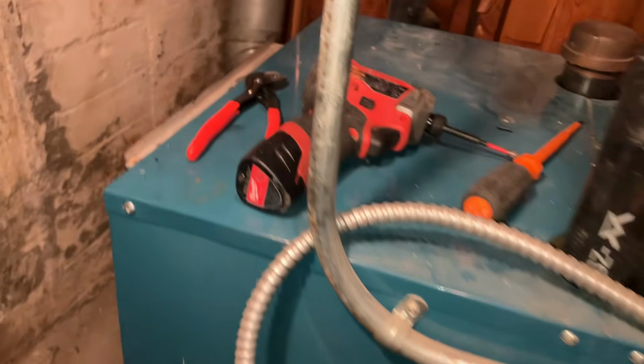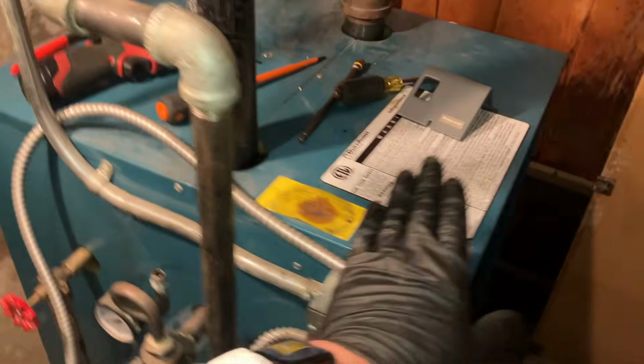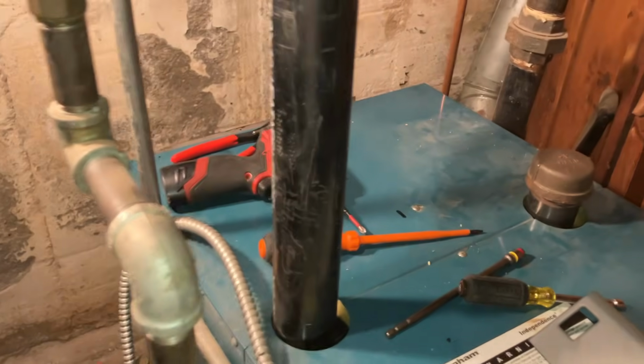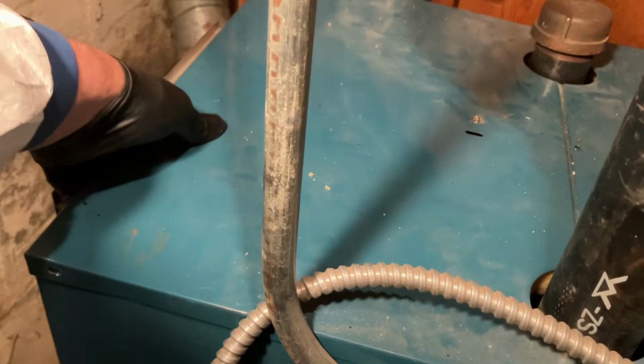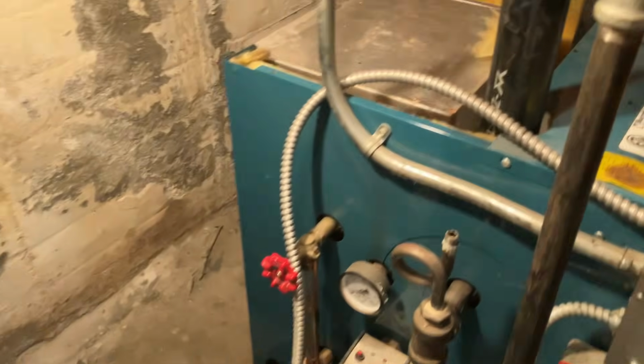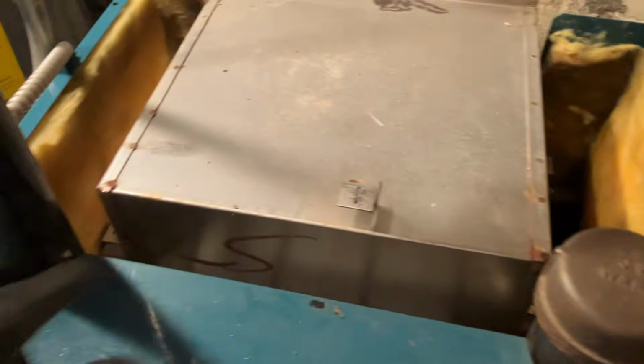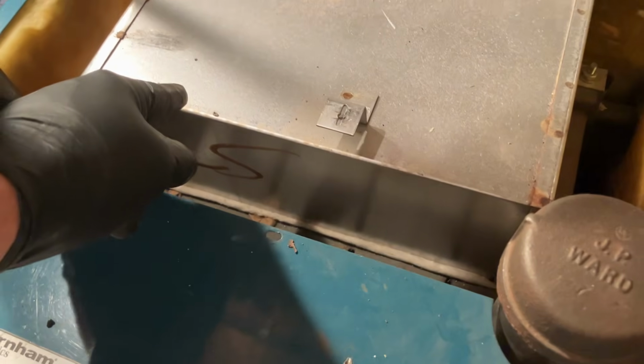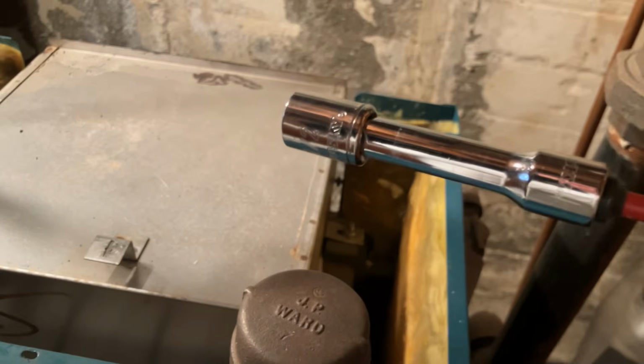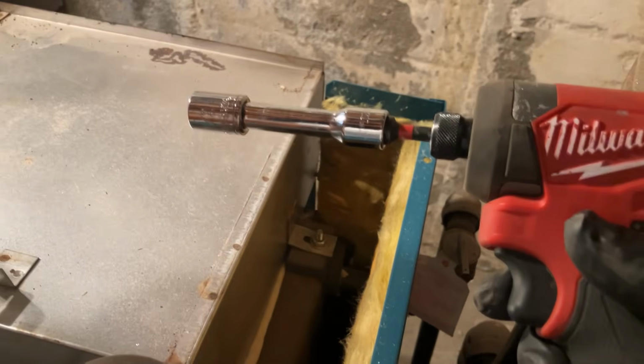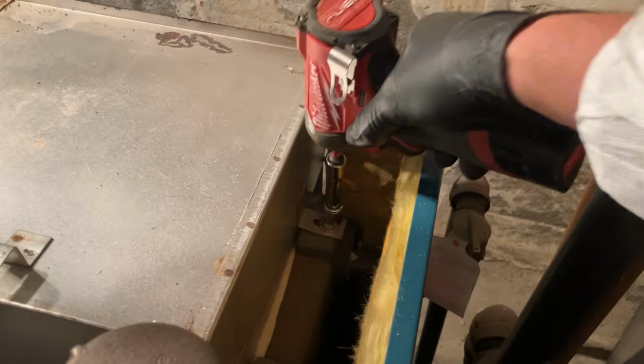Okay. I'm now going to remove the top covers with a Phillips bit. Take the top covers off. Save the screws. Okay, let's put that off to the side. Now we have the internal draft hood. We're gonna get our socket set and loosen up those 4 bolts, and that's gonna expose the top of the heat exchanger. I'm gonna use a 1/2 inch socket on an extension bit, and we're gonna take out these.